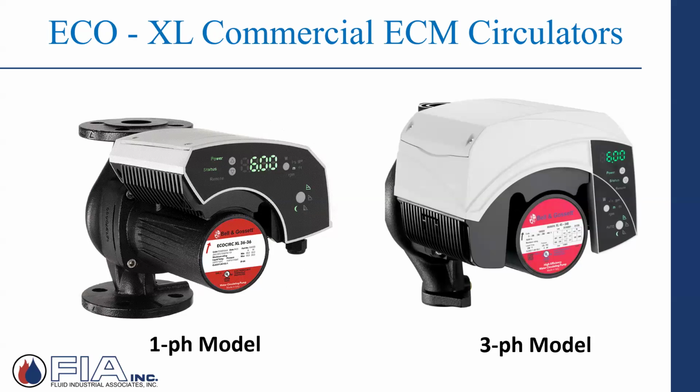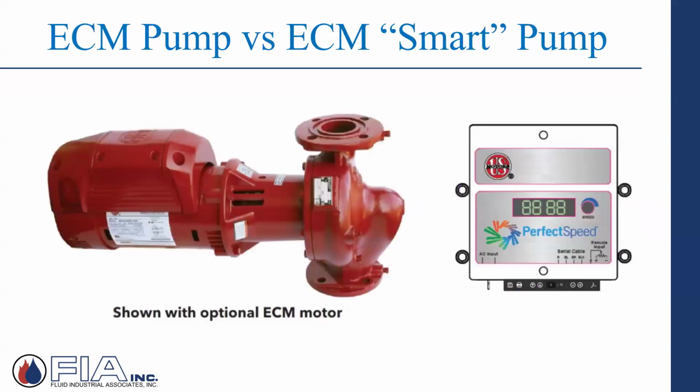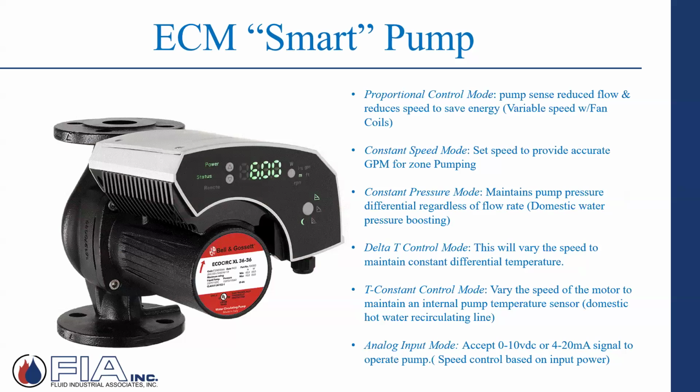So the ECM pumps are a step up, but they need some external setting or signal coming into the pump to respond accordingly. These guys, they have the drives. This technology has the drives. And what's interesting is you have this one pump with a computer on board, a printed circuit board, and because of that, you can do all of these different modes of operation with the same pump. So there's a lot of flexibility.